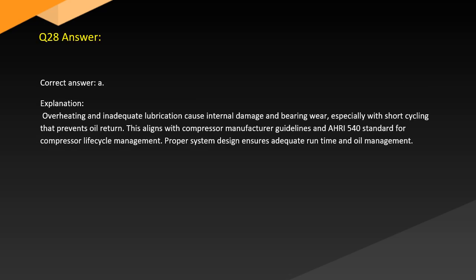Answer. Correct answer: A. Explanation. Overheating and inadequate lubrication cause internal damage and bearing wear, especially with short cycling that prevents oil return. This aligns with compressor manufacturer guidelines and the standard for compressor lifecycle management. Proper system design ensures adequate runtime and oil management.